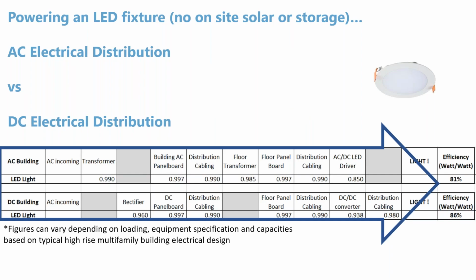So efficiency is something that's often overlooked in the electrical distribution world because ultimately our opportunities for putting in more efficient or more unique infrastructure is typically limited. But when looking at AC power distribution versus DC power distribution, in this analysis, we've added the components that the building would see between the source, being the utility coming into the building, all the way to the actual LED fixture, so the LED in the bulb that's creating useful light. And this is an analysis that shows that if we were able to remove some of the AC to DC conversions, we would actually achieve a percentage savings, between 81% to 86%. Almost a 10% improvement in retained energy consumption to drive that LED.